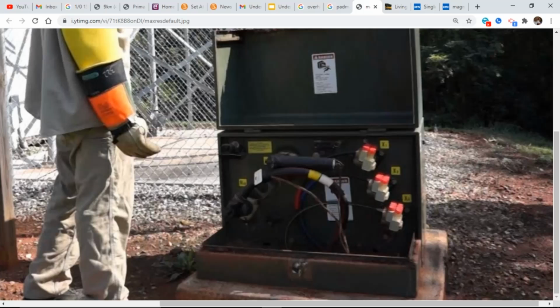Yeah. You're right. You're gonna do the same with the other phase that's outbound. It doesn't have the same phase outbound. But I can guarantee you, gentlemen, this is jacketed. Once you pull this off, it's going to want to spring back this direction. Okay. And once this makes contact with any of the secondary bars, that is a phase to ground fault, even with the jacket on the outside of it. Back to what we were talking about before, he has got a lot of extra cable here to be able to re-terminate if he needs to. So that's good information right there.